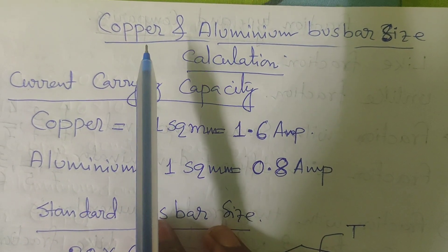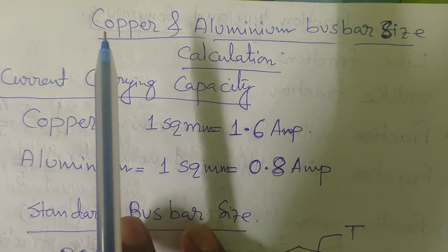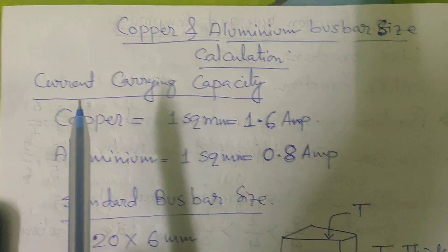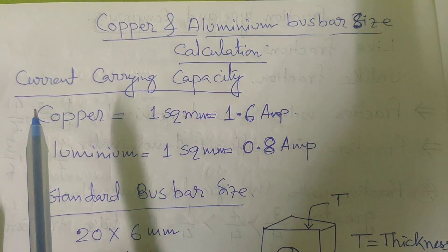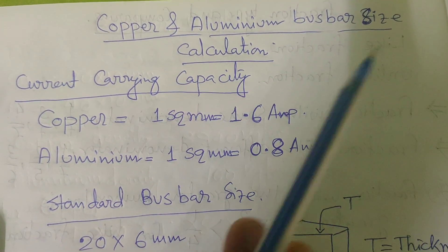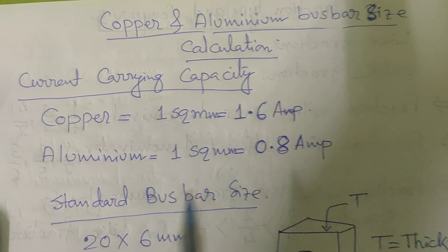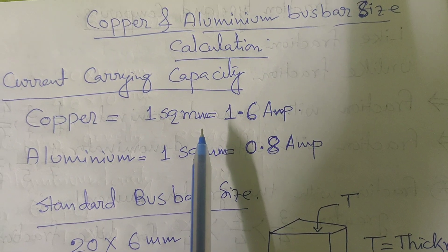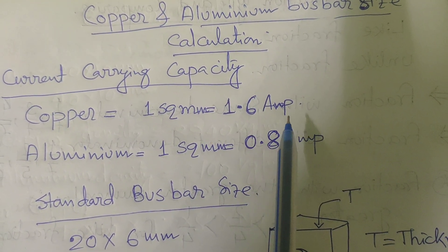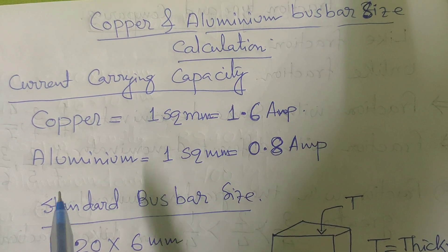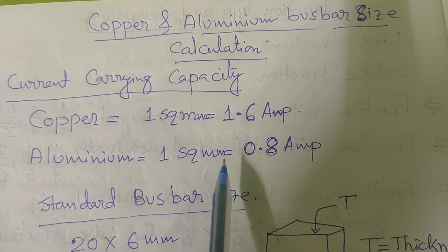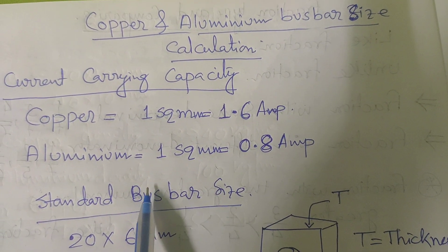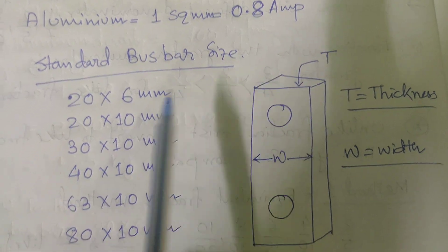Busbars are made of copper and aluminum. Now let's discuss copper and aluminum busbar size calculations. Current carrying capacity, or CCC: 1 square mm of copper busbar can carry 1.6 amperes of current, and 1 square mm of aluminum busbar can carry 0.8 amperes of current.